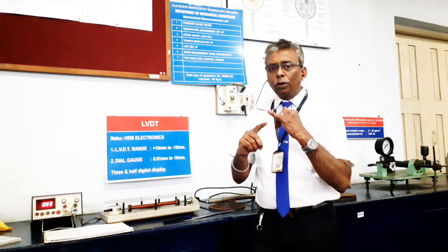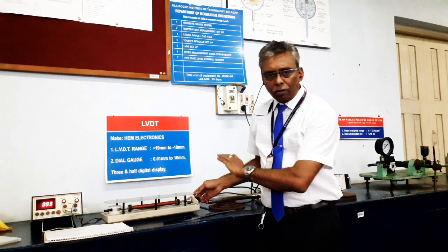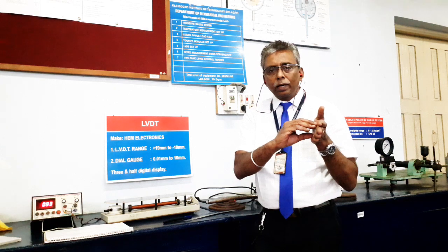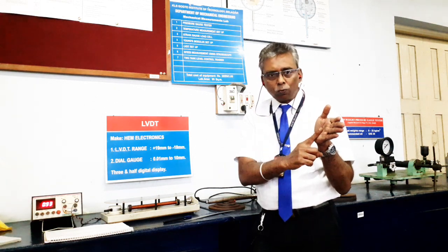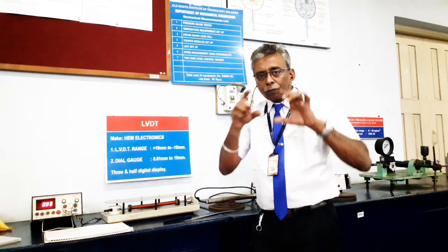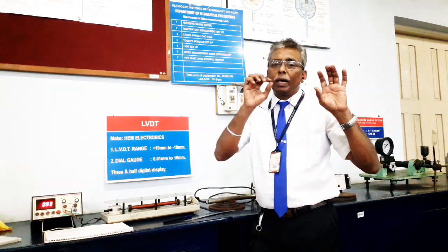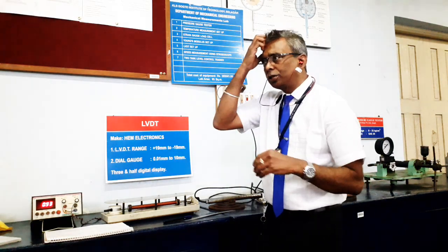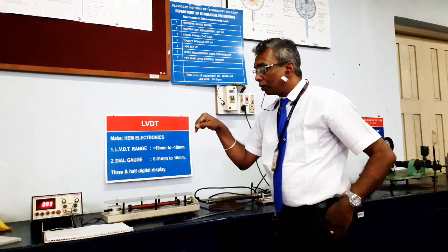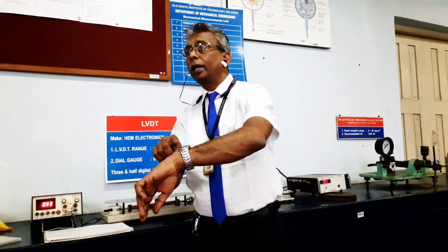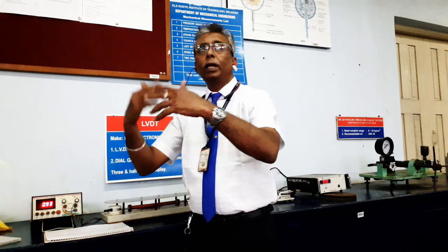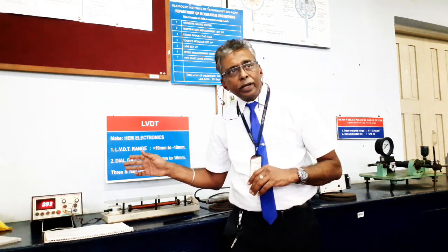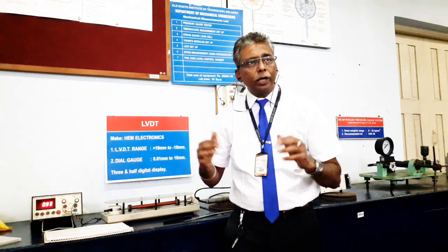One is, you have to tabulate the values. I will explain how to tabulate what are the inputs and what is the output. After that, the conclusion would be that a calibration of the given LVDT was conducted. Next, we could observe from the set of readings the maximum error that was found using this LVDT under today's circumstances. See, it may change. Somebody else may operate and the error may change. Calibration is always done with respect to date, time, everything. Tomorrow again the instrument may behave differently. Always, depending on its importance, severity, criticality, we need to calibrate the instruments on a regular basis.